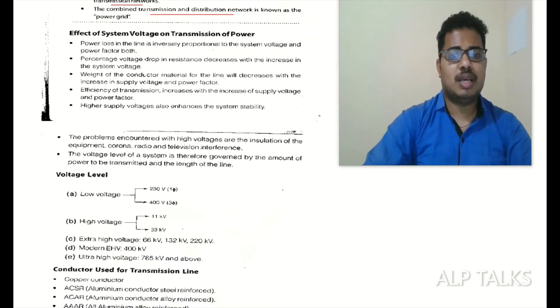Percentage voltage drop in resistance decreases with increase in system voltage. Weight of the conductor material for line will decrease with increase in supply voltage and power factor. Efficiency of transmission increases with increase of supply voltage and power factor. High supply voltage also enhances the system stability. The problems encountered with high voltages are insulation of the equipment, corona, and radio and television interference.